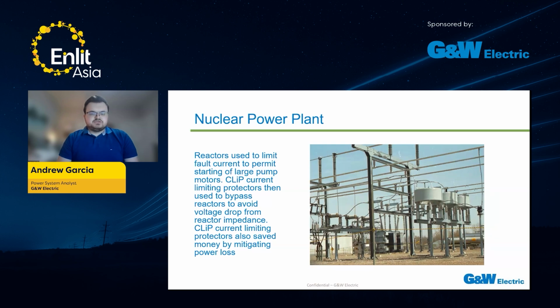How did they solve this issue? They used the CLIP current limiting protectors to bypass those reactors to avoid that voltage drop from reactor impedance. They also ended up saving the facility money by mitigating that power loss.